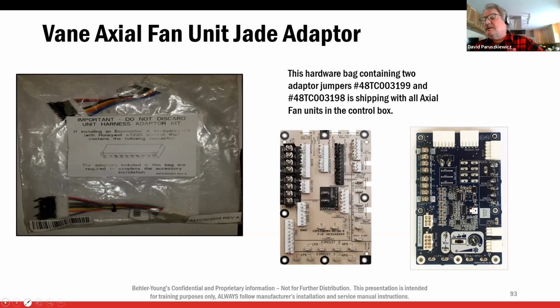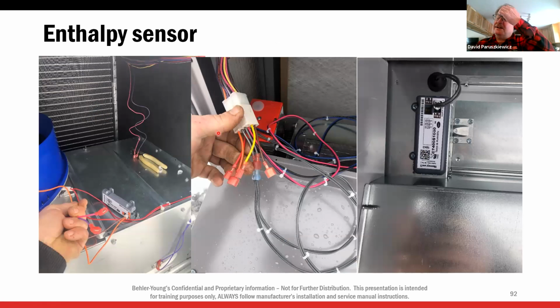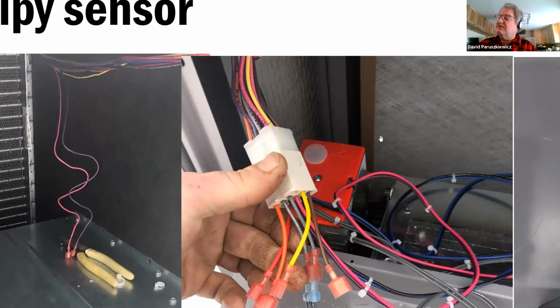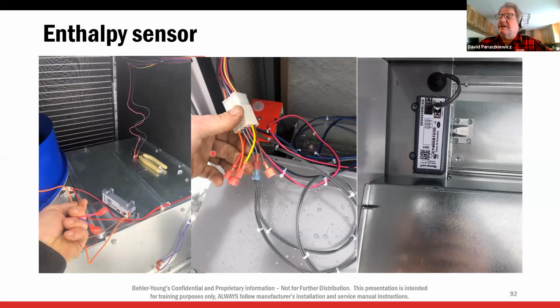All right. One other thing I want to point out. This plug right here. Now, this is where the economizer plugs in. If you've ever put an economizer in, you put the economizer in the unit. This is the return section. There's a jumper plug shipped from the factory attached to this little 12 pin. You have to unplug the jumper to plug the economizer in. Take yourself a tie wrap or wire tie, whatever you want to call it, and tie that jumper right here. Because if your economizer ever fails, we can simply unplug it and plug the jumper back in. Okay, because remember, the economizer controller locks compressors out. So do yourself a favor and keep that jumper with this plug.